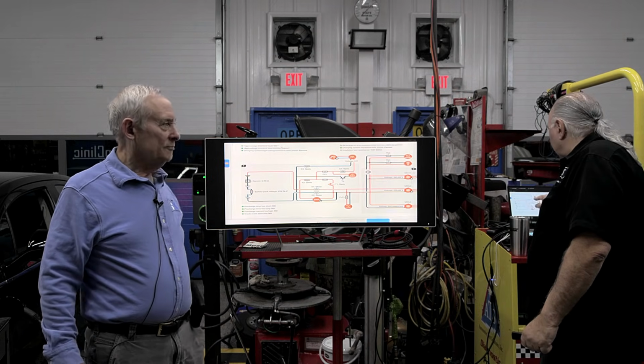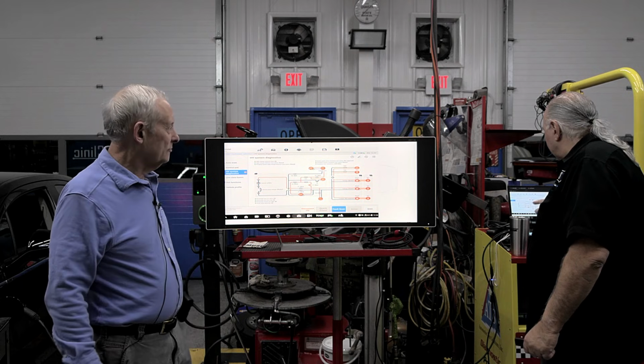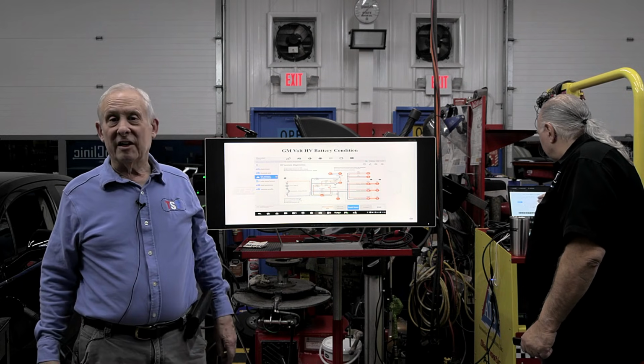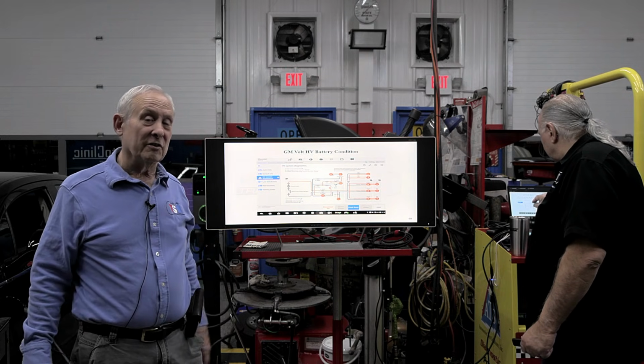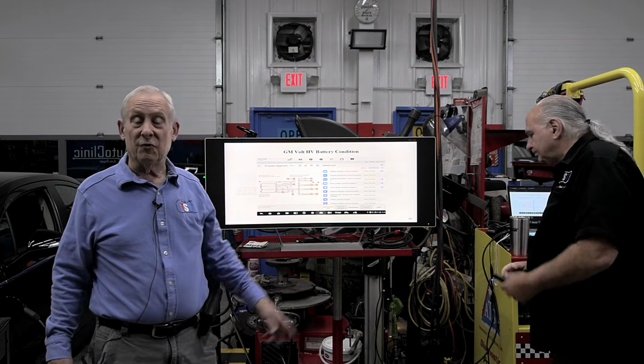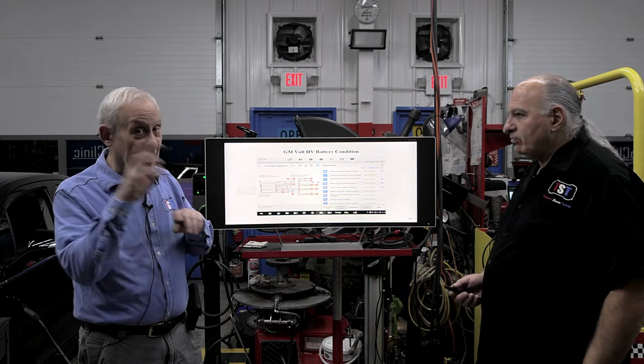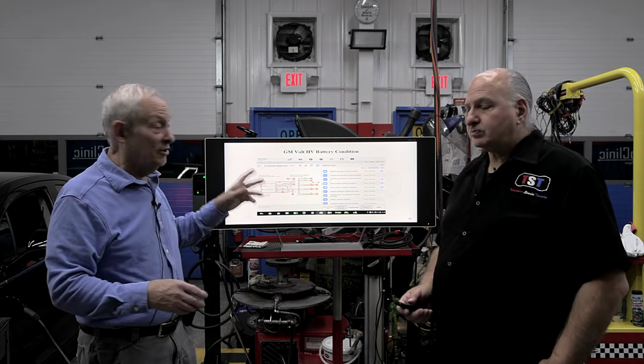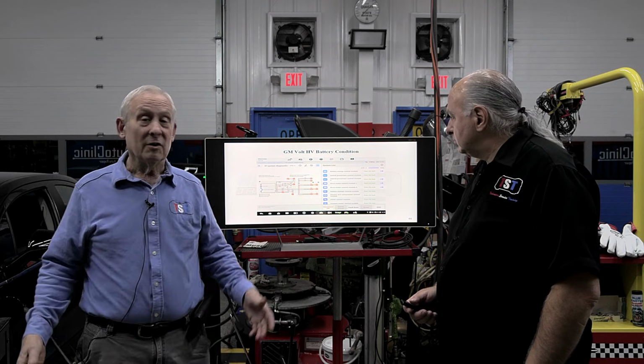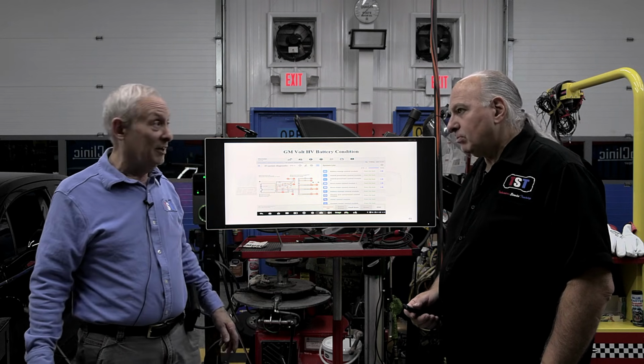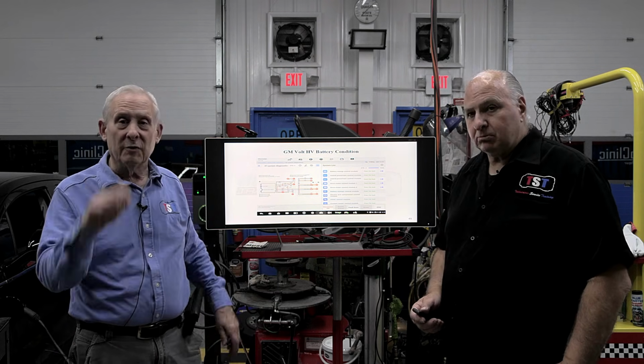We'll show you, you can do one more thing. Now by the way, just like any other tool, it's not the only tool in your toolkit. If you have an insulation fault here, you've got to go down that pathway of diagnostics - you're not doing that with a scan tool, you're doing that with a megohm meter or a milliohm meter in the case of continuity through wires.